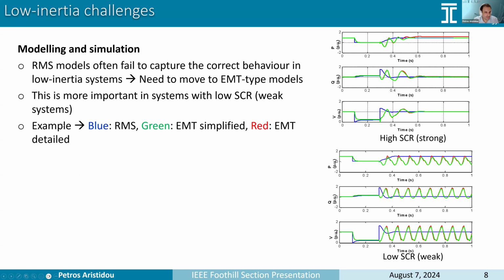This is one example that we can see here. At the top, we see the simulation of the active power variation of a unit when we have a high short circuit ratio, which means a strong system. In blue is the RMS simulation, while red and green are EMT type simulations with different accuracies. We can see that when the system is strong, while there is a difference in the simulation, at least the overall behavior is captured correctly, and the final steady state is captured correctly. When we move into a low short circuit ratio, meaning a weak system, we see that the RMS type simulations do not capture correctly all the oscillations that happen in the system or the different interactions that we have.